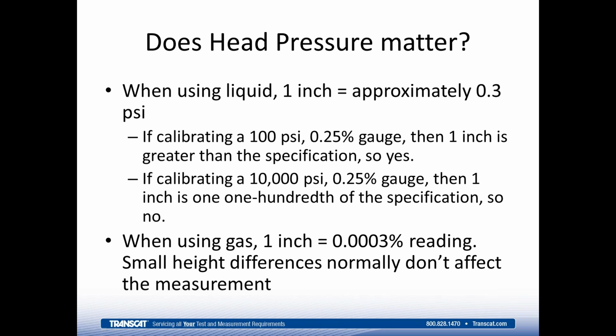If we're trying to calibrate something much more accurate, or if there's a really large head height difference, let's say that you're calibrating a gauge in situ, that is, you're calibrating it in its place of usage, and the gauge is at the top of a boiler or at the top of a smokestack, and you're standing 20 feet below it. Well, it's possible that change in elevation could result in a head height issue.